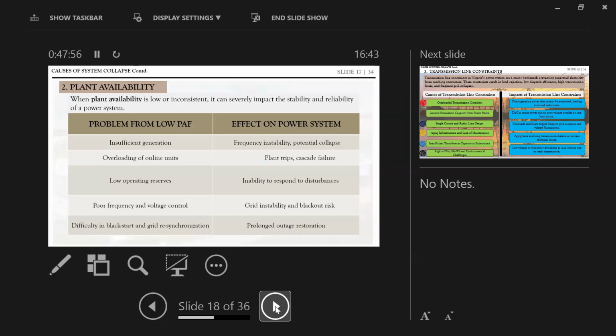Number 2 cause is plant availability. When plant availability is low or inconsistent, it can severely impact the stability and reliability of the power system. The problem from a low availability factor is insufficient generation. Effects on the power system: frequency instability, potential collapse, overloading of online units, plant trips, and cascaded failure. It can cause plant trip and cascaded failure.